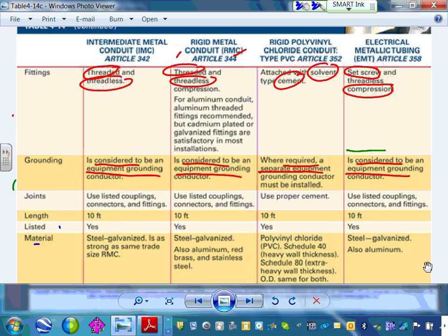The length, guys, here's what we do typically with length, how far you can go with the conduit. Typically every 100 feet, this is not code, every 100 feet you want to have a junction box or a pull box. Every 100 feet or so. If it's a straight run, you might push it for 150, 200. Now, that's rule number one.